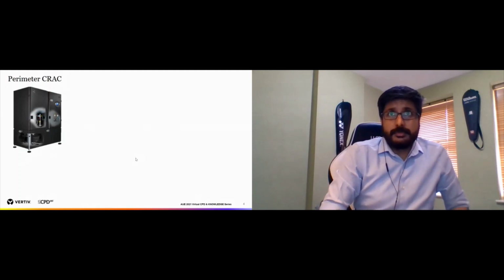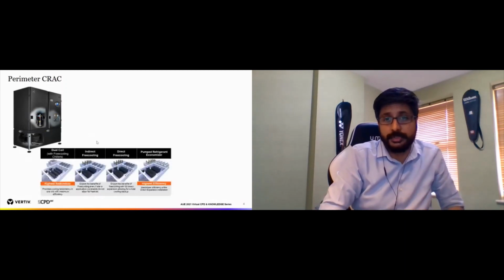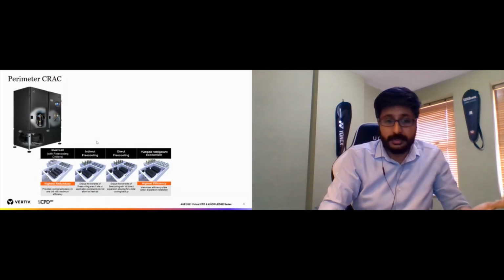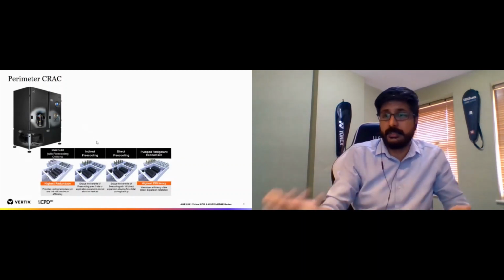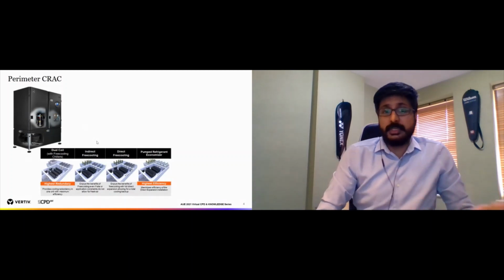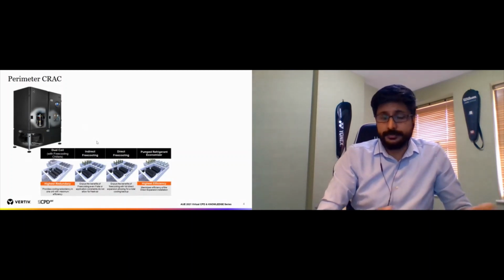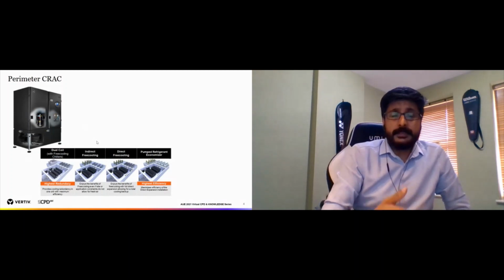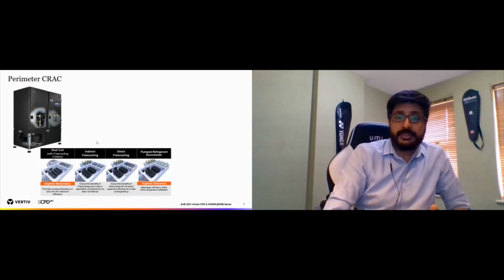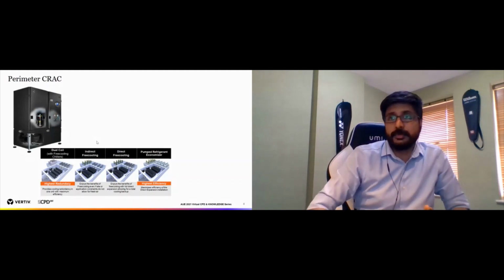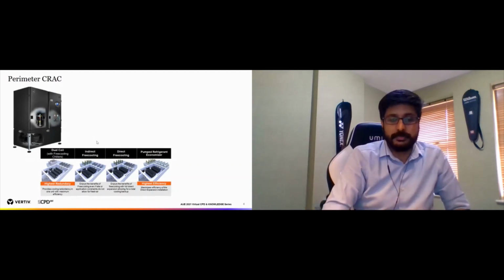Now, to bring in more efficiency, there were different ways. Initially, it was not about efficiency. Initially, it was a case of redundancy, like Russell was mentioning about N and N+1. So where do you get the redundancy? That's where we have different options. One of the options was a dual fluid unit, or a dual circuit unit, so you have a chilled water coil and at the same time a DX coil. In the case of DX coil failure, the chilled water coil can cool the room with the chiller sitting outside. Then it came to the options of how to increase efficiencies, because the DX units were bringing the PUEs quite high, or let's say the energy consumption was going really high.